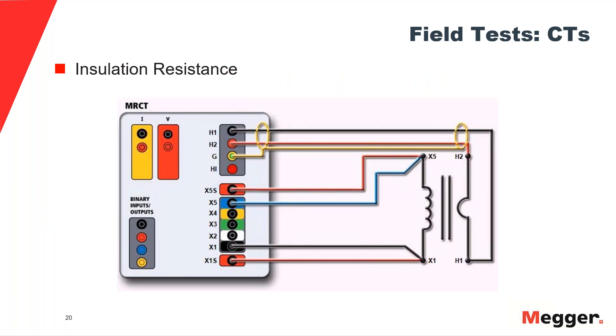Then we move on to insulation — a really important test based on what we saw in the failure data earlier. Making sure that the dielectric is still in good working condition, or detecting early signs of degradation in the CT. Typically for insulation resistance testing on CTs, we perform three different measurements: primary to secondary, primary to ground, and secondary to ground. This can be performed either with an instrument specifically made for CT testing or with simple insulation resistance testers.